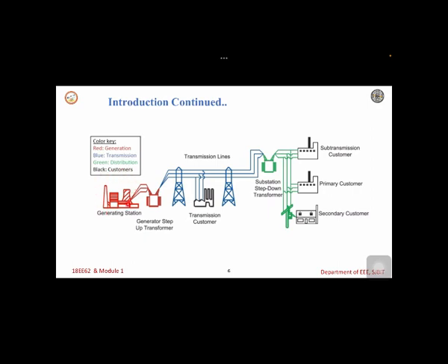So at this voltage, if you are transmitting power to the different consumers, then the transmission losses will be more. In order to reduce the power loss, we have to step up the voltage of the generating station from 11 kV to 132 kV, 220 kV, 765 kV and even more.